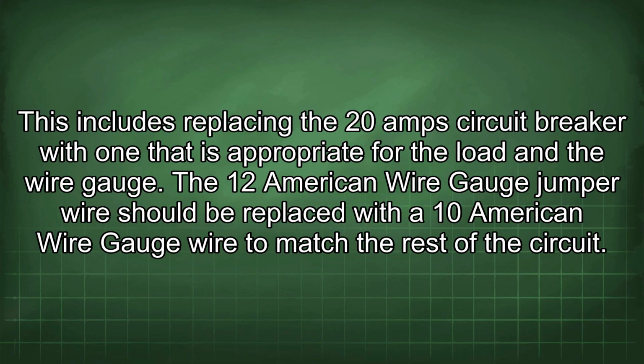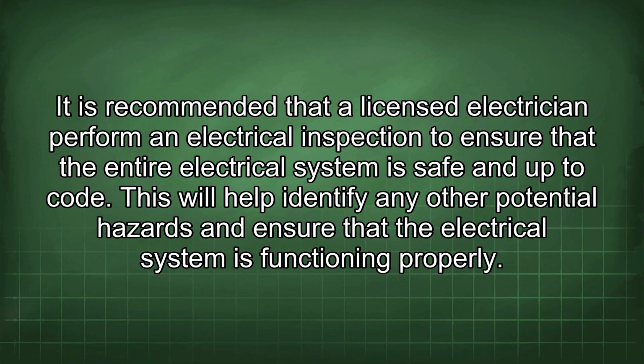The 12 American wire gauge jumper wire should be replaced with a 10 American wire gauge wire to match the rest of the circuit. It is recommended that a licensed electrician perform an electrical inspection to ensure that the entire electrical system is safe and up to code. This will help identify any other potential hazards and ensure that the electrical system is functioning properly.